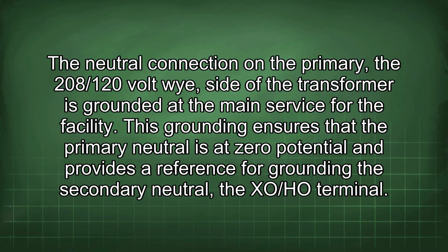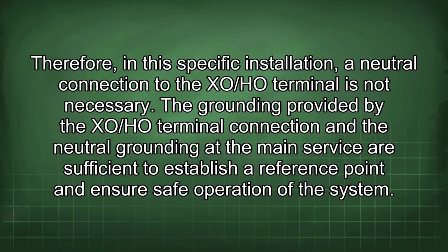208/120 volt Y side of the transformer, is grounded at the main service for the facility. This grounding ensures that the primary neutral is at zero potential and provides a reference for grounding the secondary neutral, the XO/HO terminal. Therefore, in this specific installation, a neutral connection to the XO/HO terminal is not necessary. The grounding provided by the XO/HO terminal connection and the neutral grounding at the main service are sufficient to establish a reference point and ensure safe operation of the system.